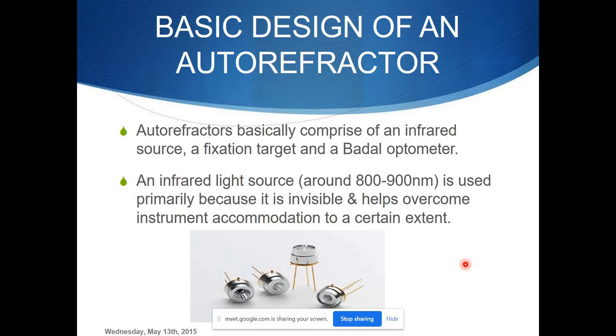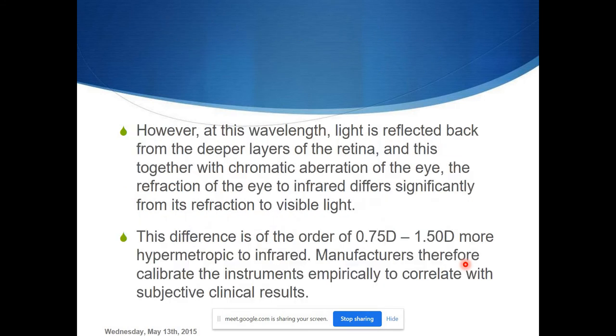Instead of two pinholes, later instruments used two light sources and two receivers. However, a drawback of using infrared light is that normal light reflects from the photoreceptors, whereas infrared goes deeper and reflects from deeper layers of the retina, varying the measured refractive error. This difference typically gives a variation of 0.5 to 1.5 diopters, mostly in the hyperopic direction. Manufacturers overcame this with mathematical calibrations that automatically adjust the result.